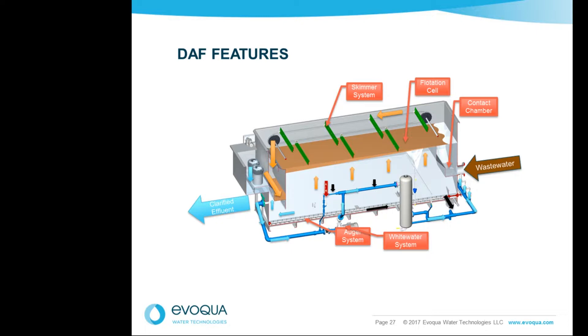Once the solids have settled and the solids have floated — hopefully more floating than settling — there has to be a means of separating the clarified effluent from those solids. There is a baffle system within the DAF that carries the flow around through an effluent weir system for discharge of the clarified effluent, either for direct discharge or further treatment downstream.